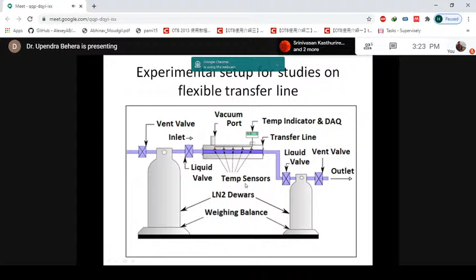And this is the typical cool down curve for this transfer line, which we have made for this 3-meter long, 20 mm ID and 26 mm OD inner bellow. And you can see these are the sensors A, B, C, D. This is from the inlet of the transfer line, where the liquid is getting in. And we have put sensors at a distance of 0.5 meter from the inlet, then at every 0.5 meter interval, up to 3-meter length.